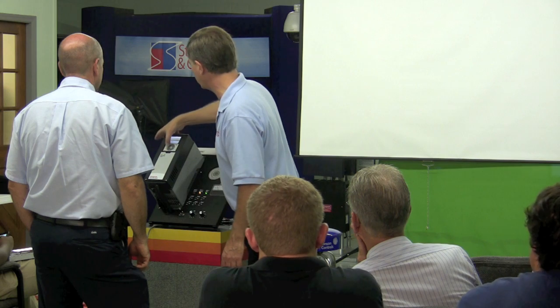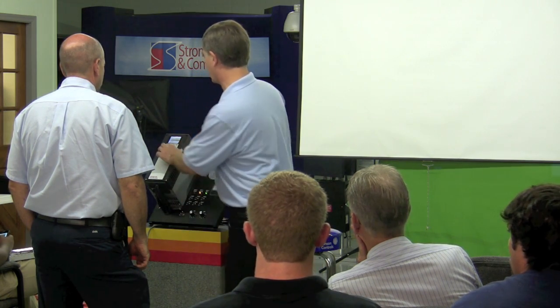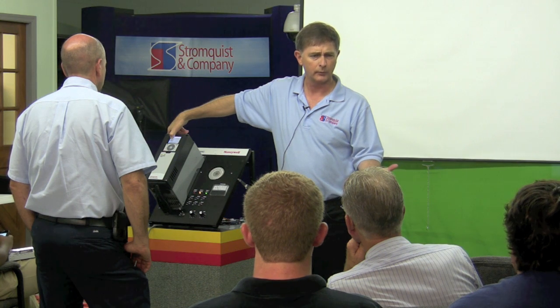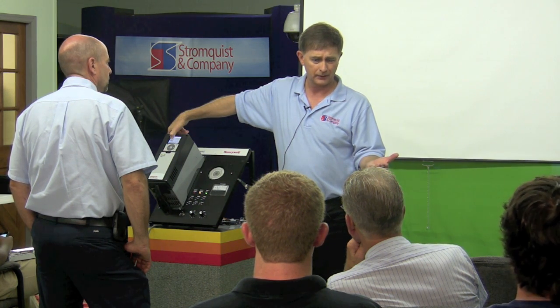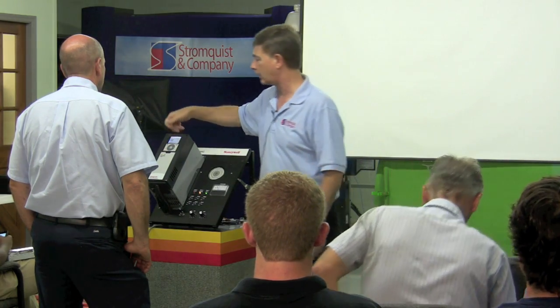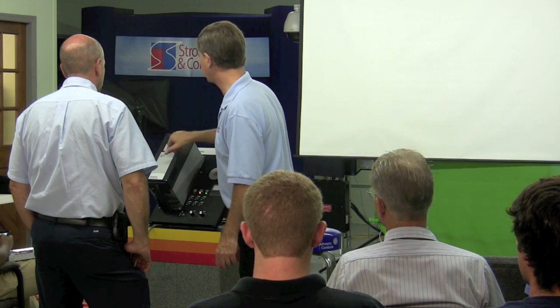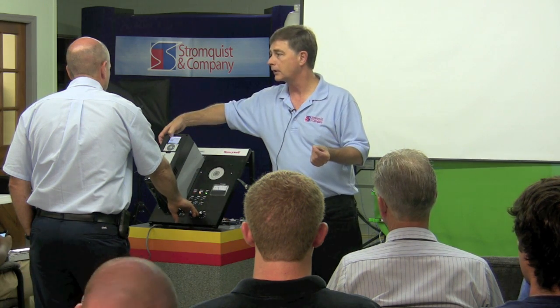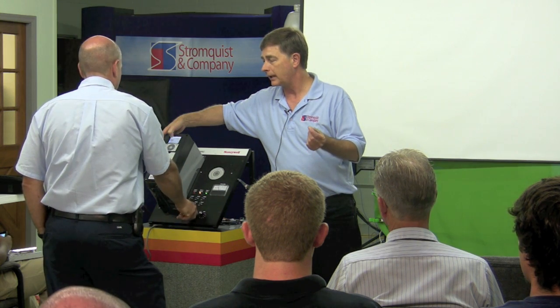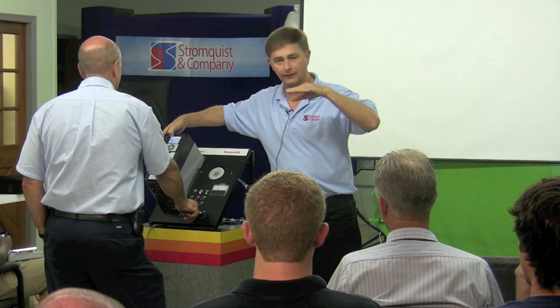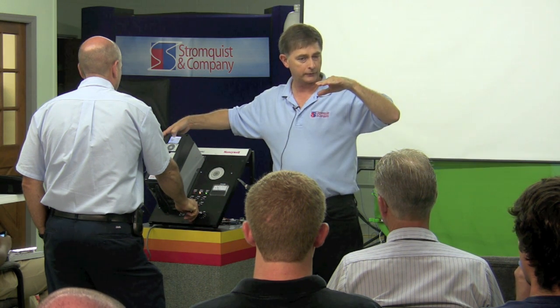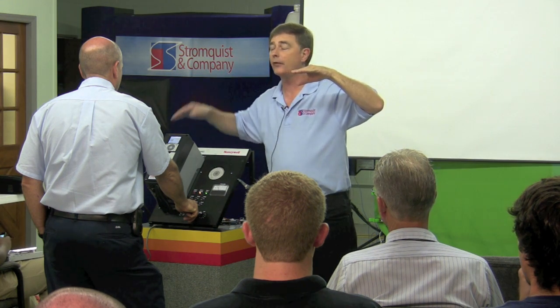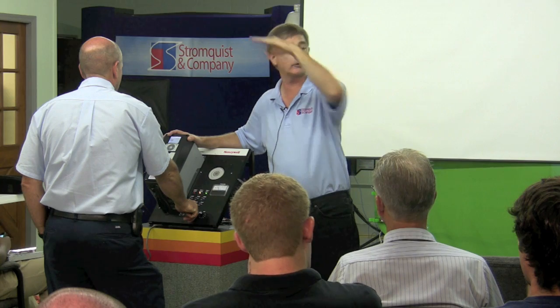So if we go back to monitor and turn this all the way down, what we'll see is the bottom frequency is 20 hertz. That's a pretty good minimum to run it. There may be times when you want to not go below 30 hertz or whatever — that's easily changed also. But if you increase your A1 signal, which is your zero to 10 volt DC signal, and just barely increase it, you'll notice the frequency is rising. If you bump it up and hit 24, you'll notice it'll stay there on the output of 24. You raise it a little more and it doesn't raise — it stays at 24. Then when you get beyond that masked frequency, it'll pick up and start ramping up.